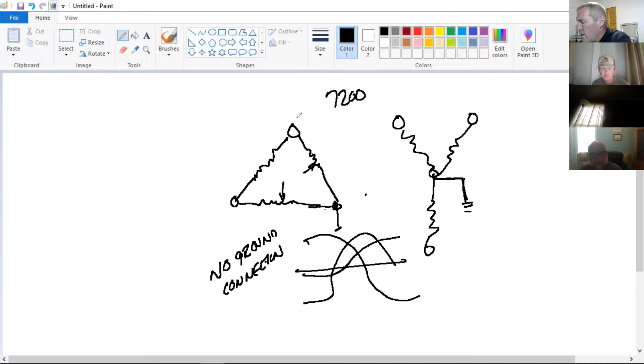But in delta, it's working on the concept of 12,470 all the time if I'm using a generation of 7,200 volts phase to ground. Difference in potential between all three coils. And you'll notice in the Y, I'm going phase to ground, phase to ground, phase to ground. In delta, where am I going? Phase to phase to phase. That's why I'm getting 12,470 all the time as the output on it.